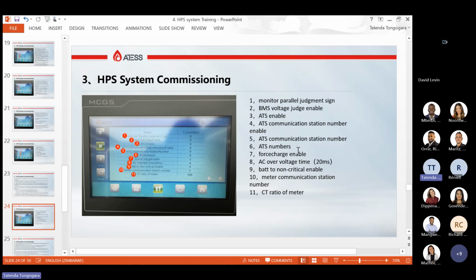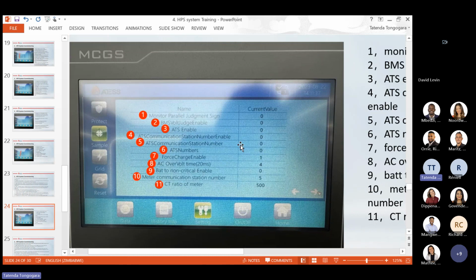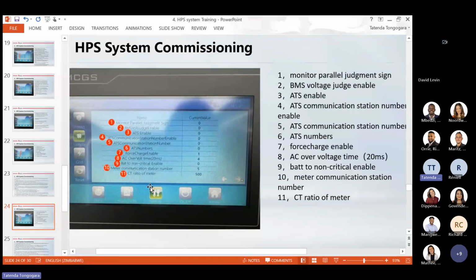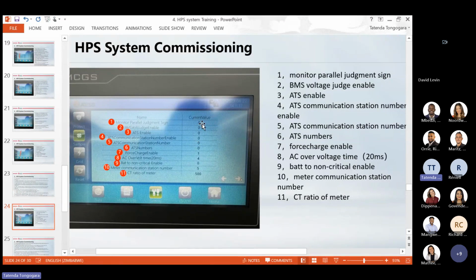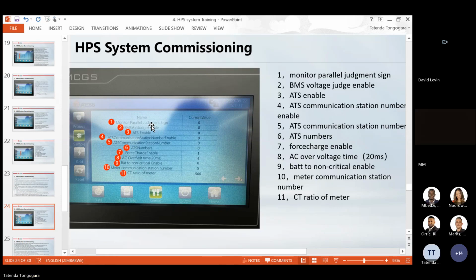In the event that you have 2 machines in parallel and you are using our analog to monitor your system, the monitor parallel judgment sign should be set. If you have 2 machines, you just set it to 1, then the analog will monitor all the devices, and on your platform it will sum the PV from inverter 1, inverter 2, inverter 3, and then display. If it's 0, it will only display for one inverter. So you have to set it to get the totals of your PV and your load.